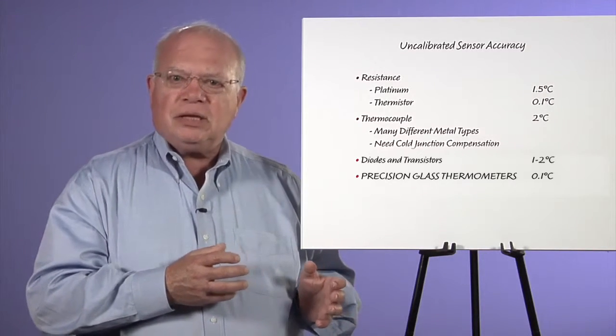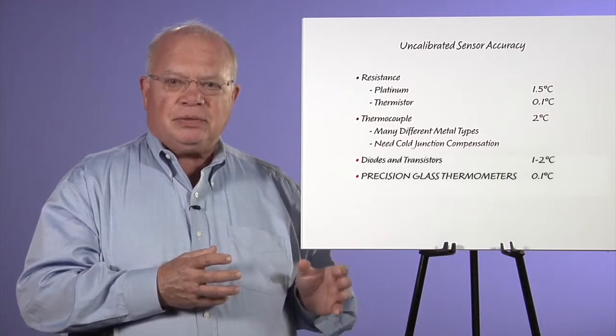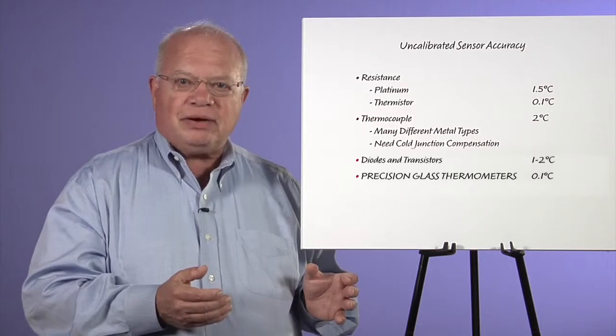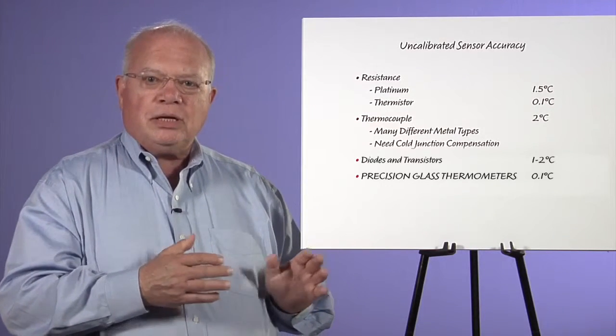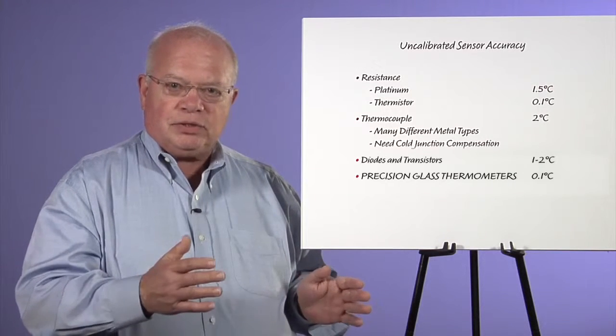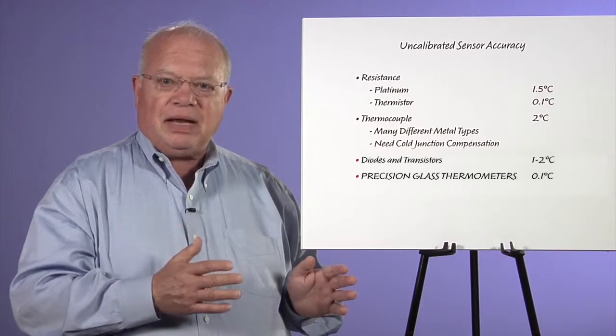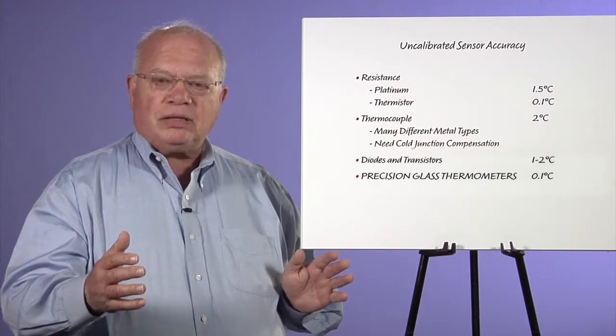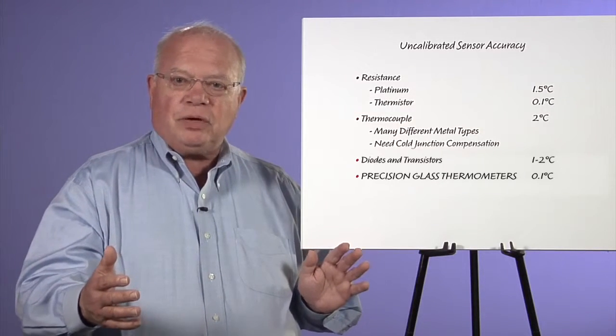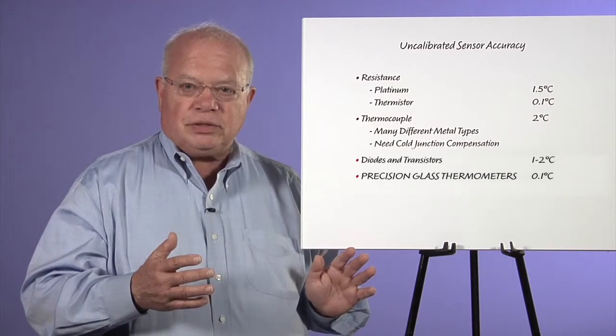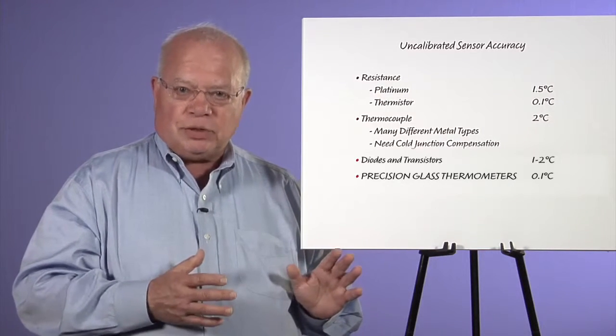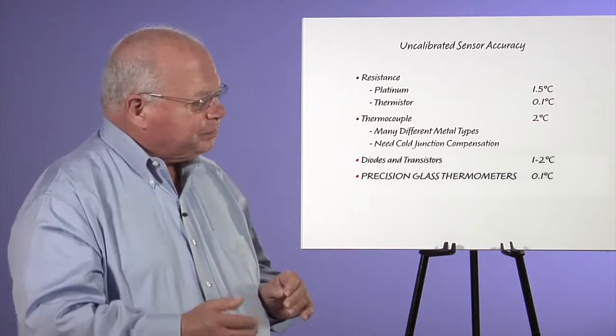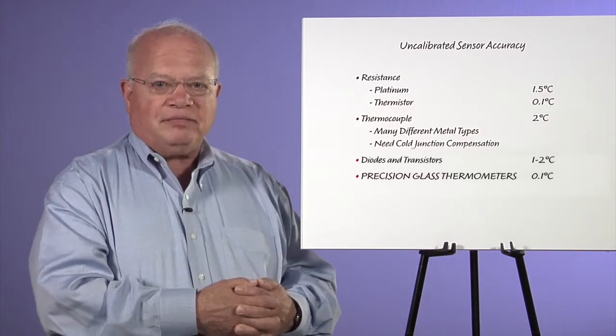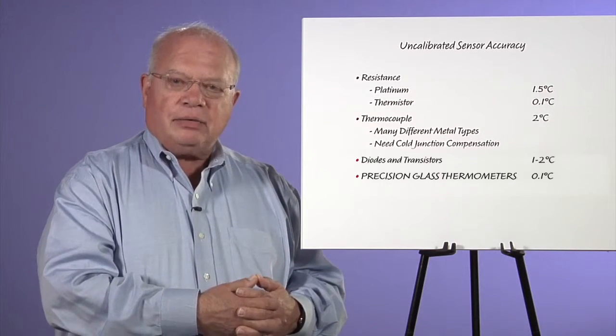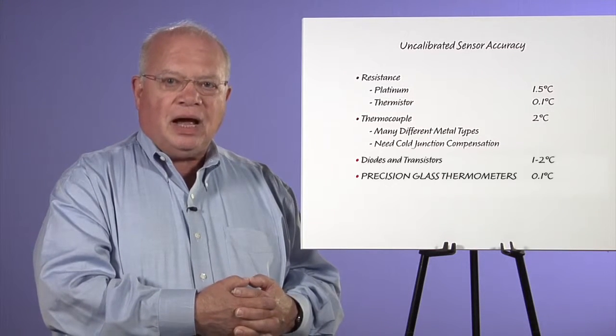Thermocouples put out microvolts. Their output is proportional to the temperature difference between the cold side and the hot side, and they actually generate voltage. The error is usually specified at max temperature differential, which is different for different thermocouples, and can be anywhere between 1 and 4 degrees for an uncalibrated thermocouple. But if a thermocouple has a 400 degree C range and you're only measuring 100 degree C, you have 1/4 of the max error because you're not using it over the full range. Diodes and transistors are not manufactured to be temperature sensors, but the diode and transistor characteristics are very consistent with temperature, and that can be converted into temperature.